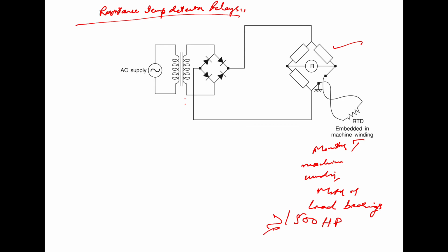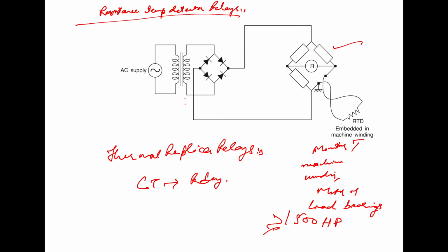Now this RTD is an excellent indicator of average winding temperature. However, it is influenced by the ambient temperature, ventilation conditions and recent loading history. Several types of RTDs are available for use in temperature monitoring, for different temperature ranges. These are available in the market. Now, one more relay is the thermal replica relay, which is designed to replicate within the relay the heating characteristics of the machine. When the current from the CT secondary passes through this relay, its time overcurrent characteristic parallels that of the machine capability curve at moderate overload.